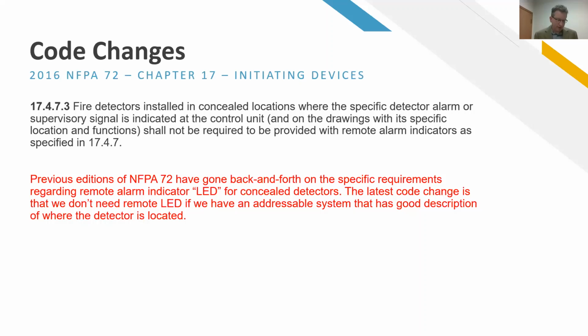The code's getting smart and saying that's not necessary if you have an addressable system where that detector has a unique address, and you can put a description. You can say it's the 3rd floor electrical room smoke detector. So if you know where it is, why do you need to have an LED to help you further define where that device is? So just something to be aware of. And it's great for everybody because it doesn't make us have that redundant LED to help find that detector.